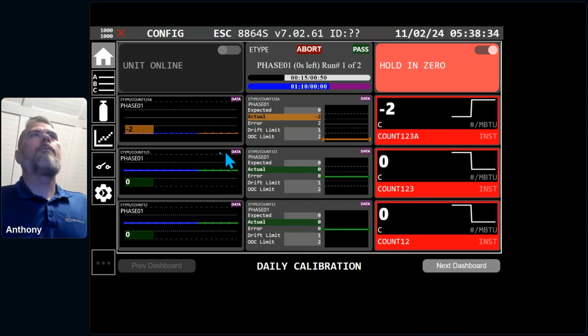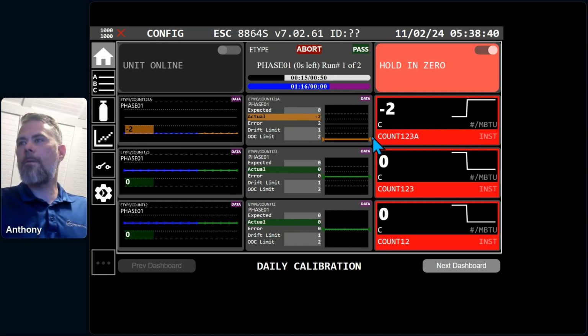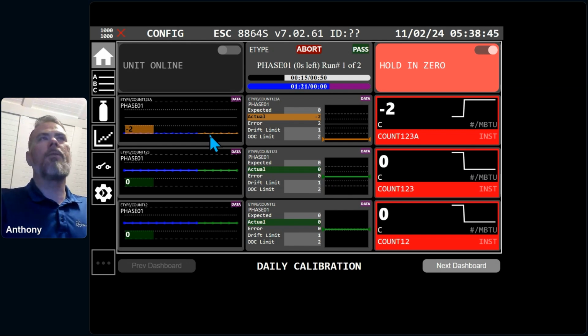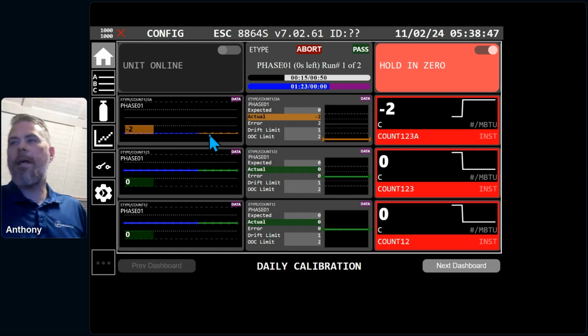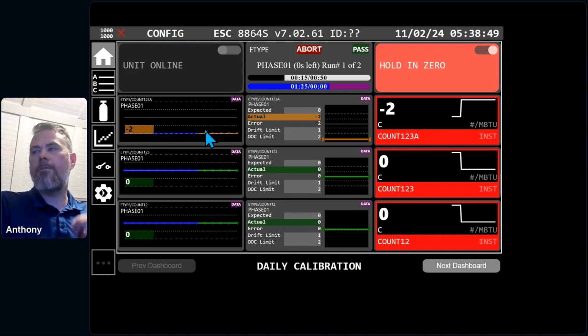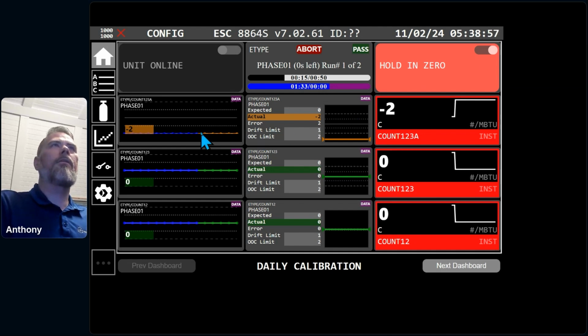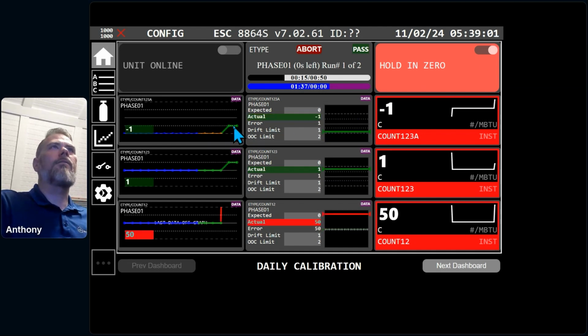Now, the status bar up here will be blue when we're not taking on data and purple when we are. So I'm going to go ahead and release this. Oh, before I do, I want to mention the trend only shows status for the number of data points that match the configured data time as data points continue to come in. Now, it looks like it's static because this is a test configuration and it's not moving around, but as the minute flips here, you'll see that we'll start to get new data points where we can recognize that they're new and that we're now passing.